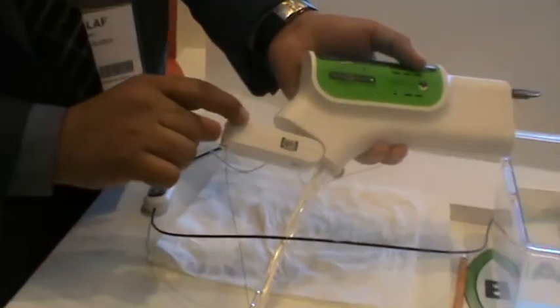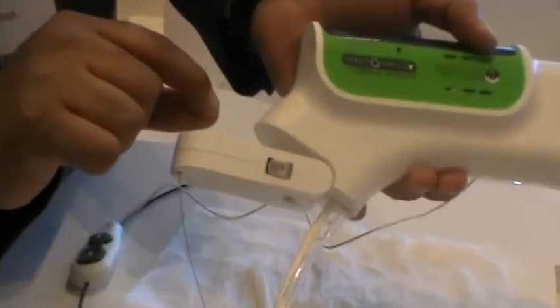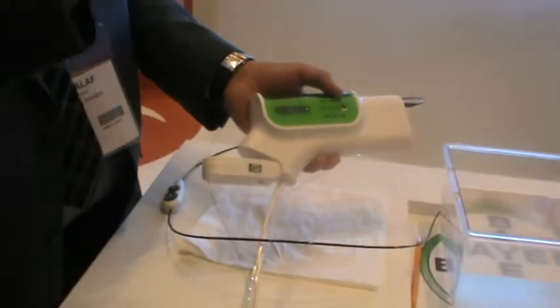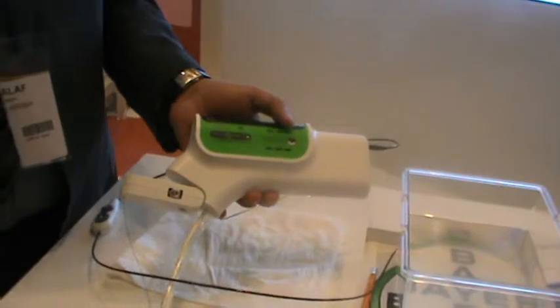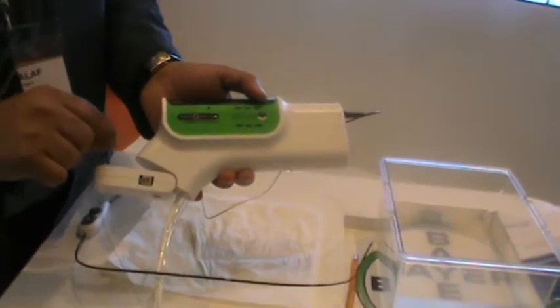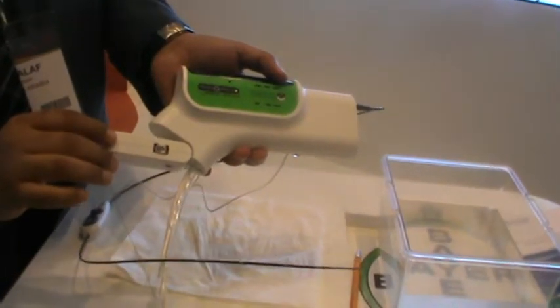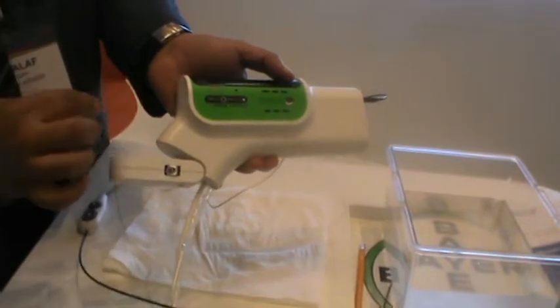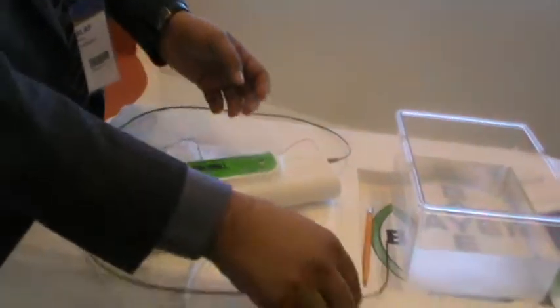Another safety feature in the device is what we call the guard for the wire, because this guard will keep the wire from spinning. When you have a 70,000 RPM rotating device, you expect some movement of the wire, and this guard will prevent spinning of the wire. It also has a loop which indicates that the wire is still moving within the catheter.